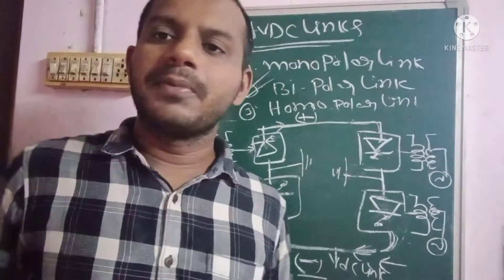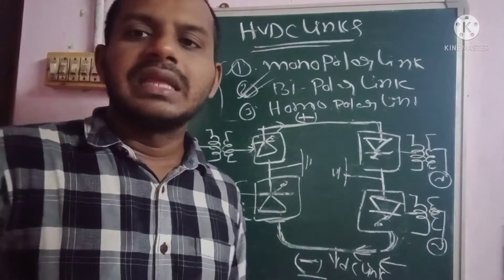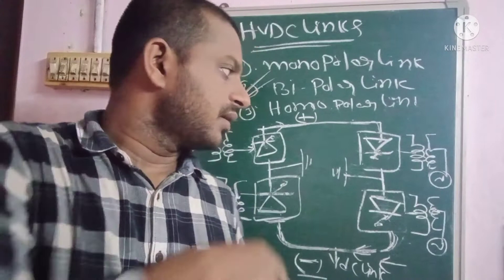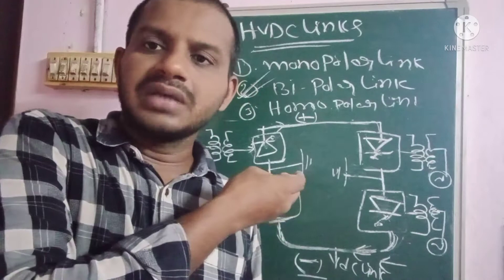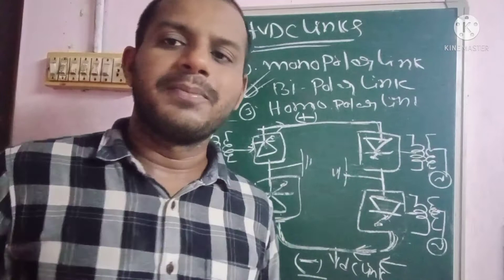The disadvantage of the bipolar link is that the maintenance cost is high compared to the monopolar link, because two conductor links are used. The cost of the converter station is also high. Additionally, losses including radio interference losses and corona losses are high when compared to the monopolar link.